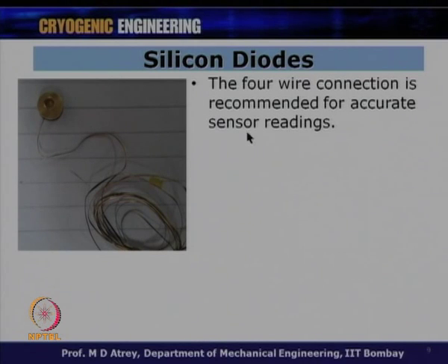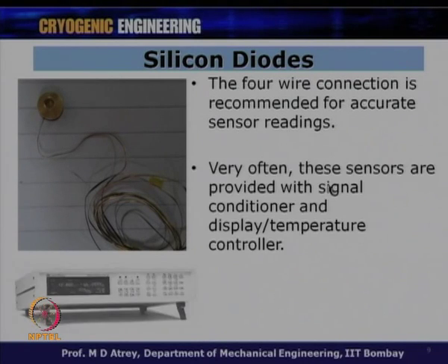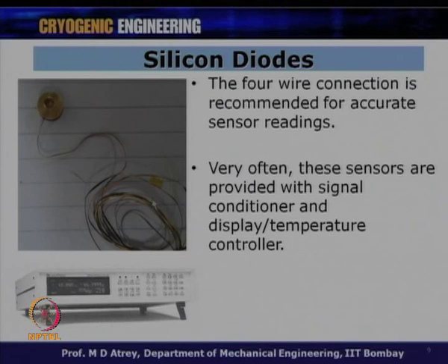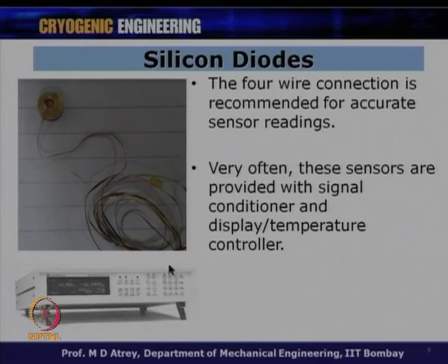A four-wire connection is recommended for accurate sensor reading. These sensors are often provided with a signal conditioner and temperature controller display. One can select the kind of sensor on the display, and calibration curves are normally loaded in, so the calibration curve for a particular diode can be directly fed to the temperature controller and displayed.